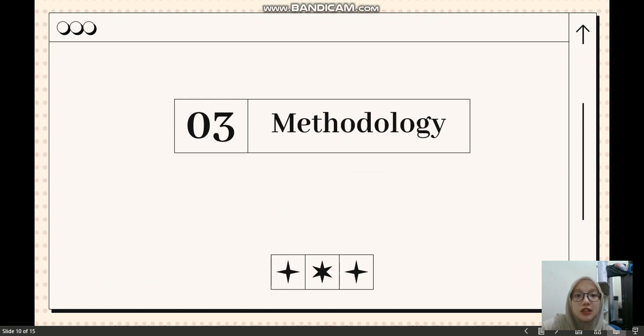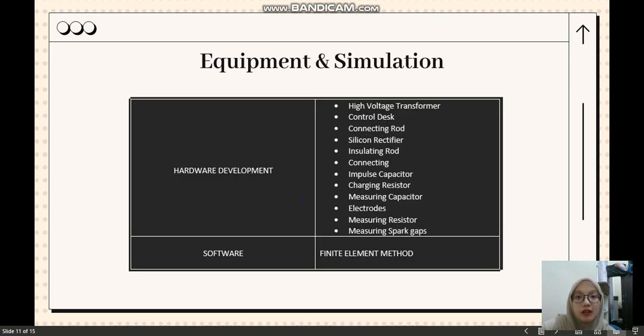Okay, number 3 is methodology. This is the list of equipment and simulation, hardware development. For this project, we use a high voltage transformer, which produces AC high voltage 140 kV, control desk, connecting rod, silicon rectifier, insulating rod, connecting, impulse capacitor, charging resistor, measuring capacitor, electrode, measuring resistor, measuring spark gaps. The software is finite element method.